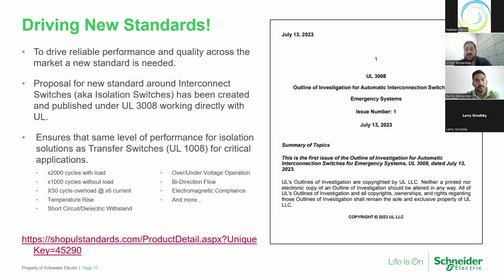But then it goes a step further, brings in other pieces that are unique to this application, such as support for bidirectional flow. Transfer switches are usually tested and qualified to power flowing from the sources to the loads, as we've talked about. But in this case, since power can flow in both directions, every single test essentially that was done to qualify it has to happen twice, once with the power flowing downstream and again with the power flowing upstream. So the first step is creating this standard so that such a product can start driving some industry standardization, since it is kind of the Wild West out there around these kinds of solutions, and drive some level of guarantee to customers and users of the reliability and robustness of such products.